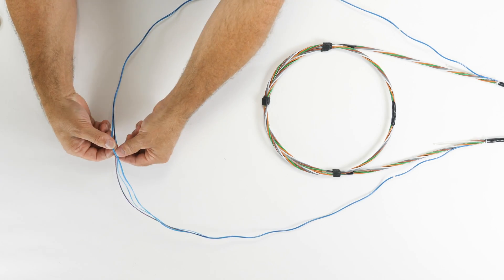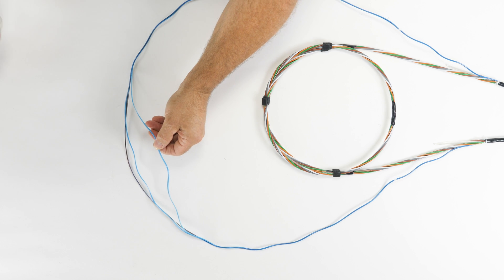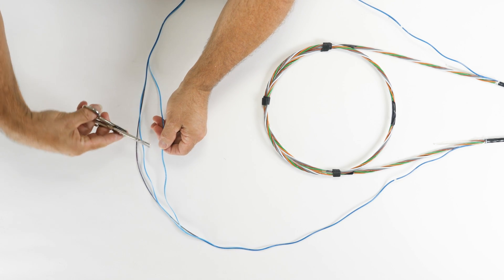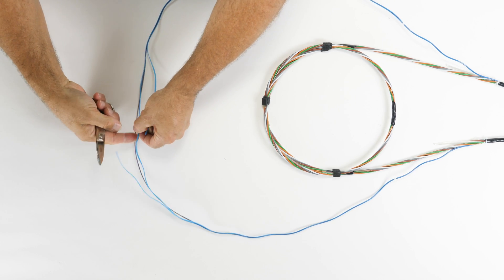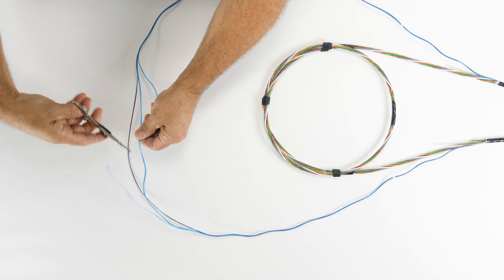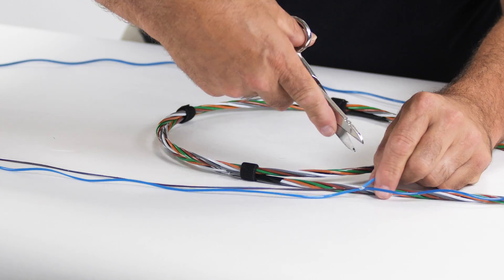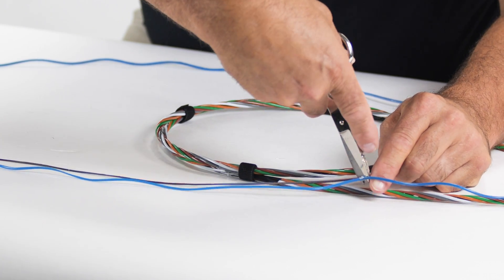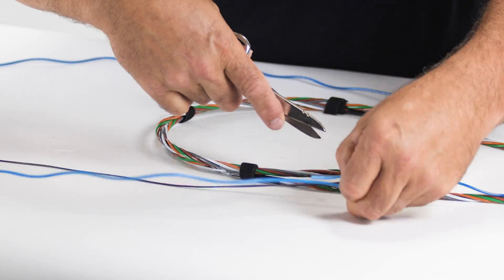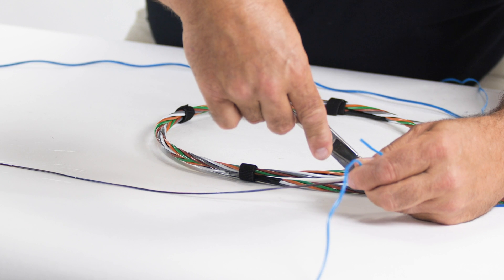Now that the slitting process has been performed, separate the two sides of the buffer tube from each other while taking care not to damage the optical fibers. When the two length indication marks are reached, a buffer tube ring cutter or scissors can be used to individually remove each side of the buffer tube jacket.